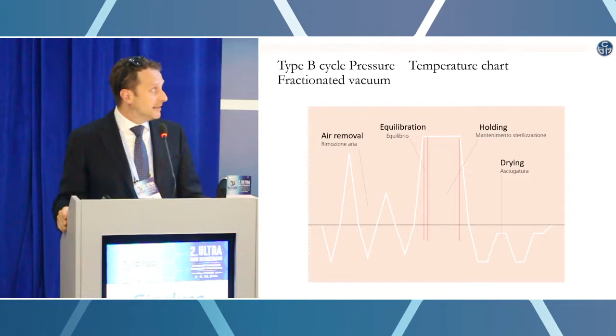Once again, it is of paramount importance to remove the air from all the load before proceeding to sterilization. Just to give you a quick comparison, if you take a simple glass and a basin of water, and you turn the glass upside down and try to push it into the water, the water will never touch the bottom of the glass, of course, because there is air trapped inside. In the same way, if you have air in the load, the steam will never touch the surface, so it will never sterilize.